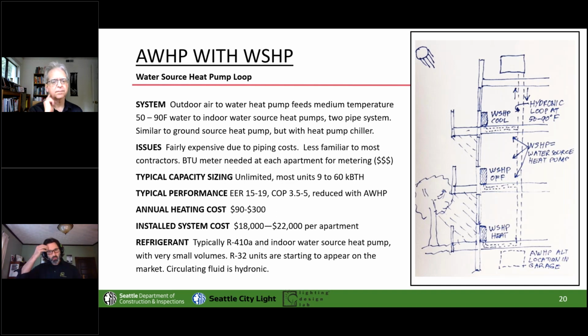So you would have that air to water heat pump or heat pump chiller, same thing, sitting up on the roof or sitting down in the garage. There's some benefit to putting it into the garage, like Duane said, because you get slightly warmer winter temps. And it would have maybe more like a fat spot in the pipe than a real tank. And then you would have all of that loop volume running around in a closed loop, so it never brings more water in. It's just sitting there circulating, and the water source heat pump either puts heat in or pulls heat out of that loop depending on its need. So there's no more water, and there's not a lot of storage beyond the chiller.